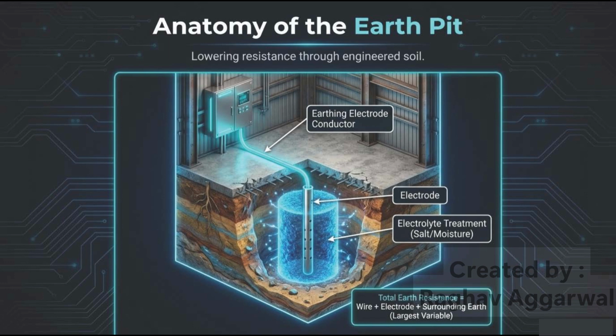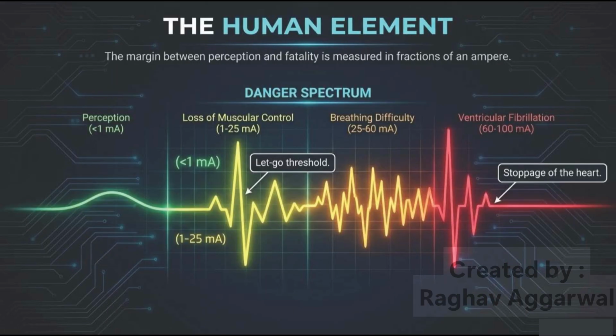For maintenance personnel, this emphasizes why periodic testing of earth resistance is important. Changes in soil conditions can affect system performance over time. The effectiveness of an earthing system depends heavily on maintaining low resistance in the earth connection. Electrical safety is ultimately about protecting people.